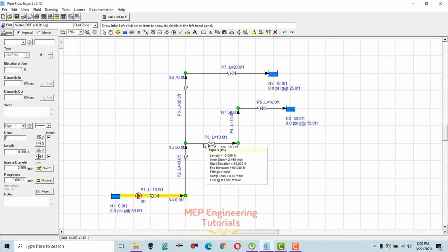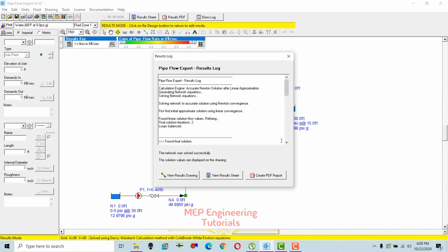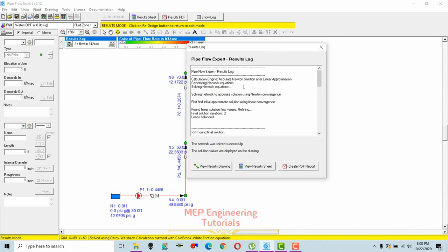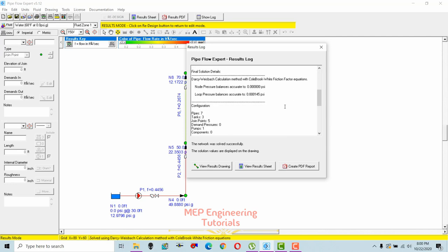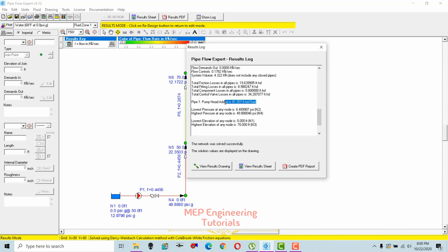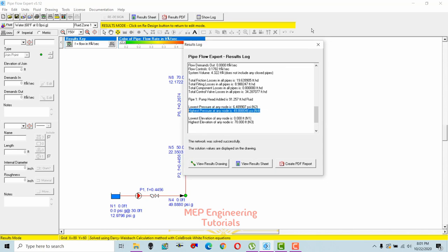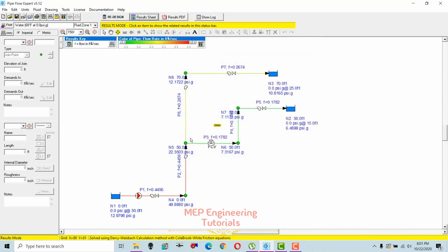To generate results and calculate the pump head, click the 'Calculate' button. A dialog box appears confirming the network was solved successfully and solution values are displayed on the drawing. The calculated pump head is 91.257 feet. The dialog also shows the lowest and highest pressures at any node. Close the dialog to view results on the drawing area.